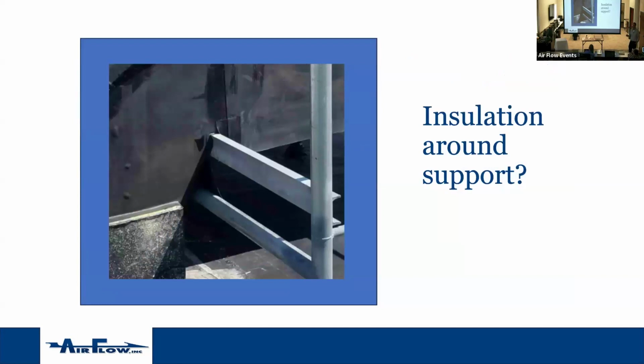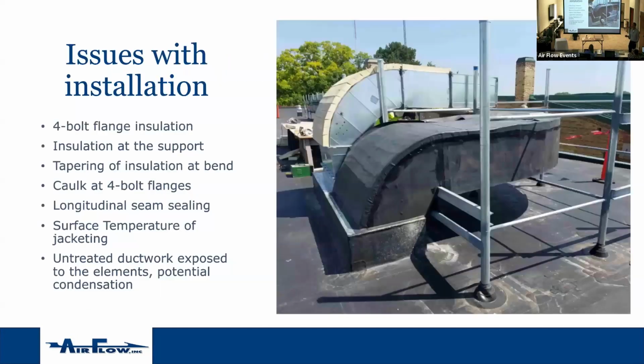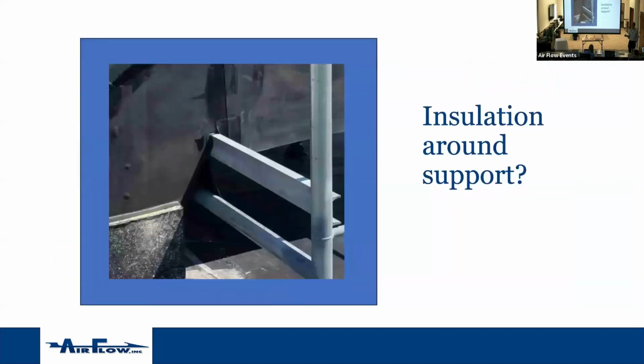A bigger issue is, we saw a couple slides ago that ductwork starts off as a piece of metal and then it sits on the support. So how do you insulate that? Well, you just don't. The metal sits on the support, and then you kind of cobble some wrapping of insulation under the support. That doesn't make any sense because you compressed your insulation. And are you going to wrap around this? Who knows what goes on in the field? It's probably not a detail that most engineers can really sort out. You've got the support, you've got the metal ductwork on the top, and then you kind of insulate and cobble around and do the best thing that you can.